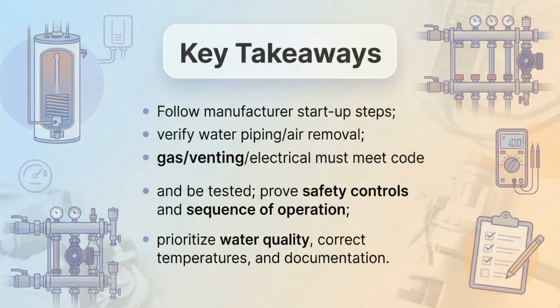The takeaways are: start with the manufacturer's procedure every time, pipe and purge correctly so flow and air removal are solid, make gas, venting, and electrical code compliant and test them, prove the full safety chain and operating sequence, and for long-term reliability, focus on water quality, proper temperatures, and good documentation in a service log.